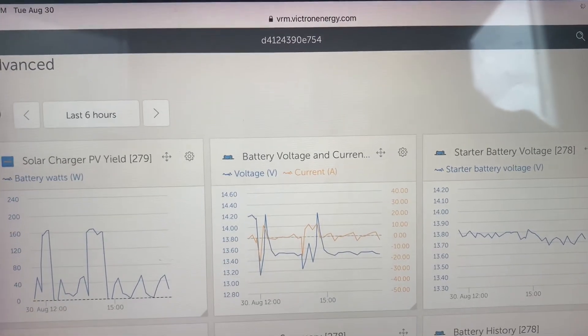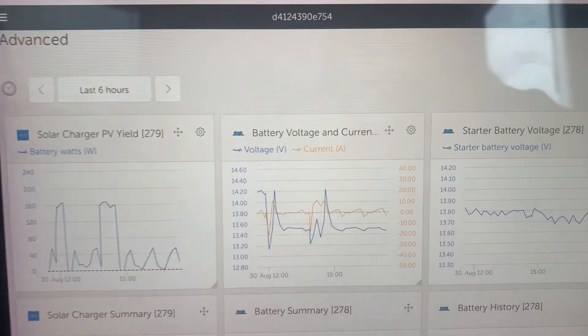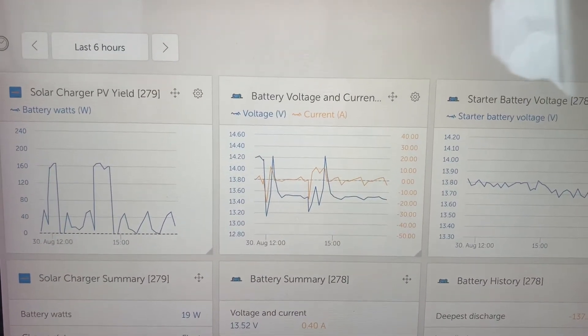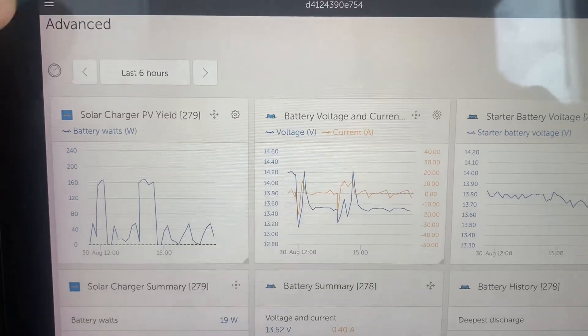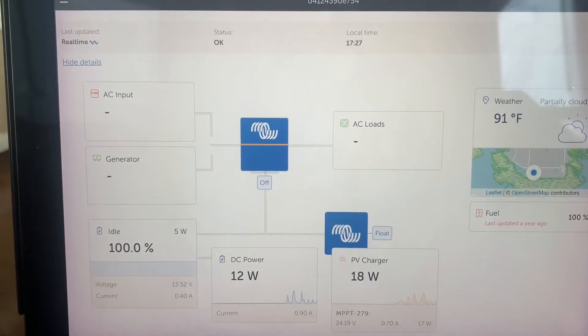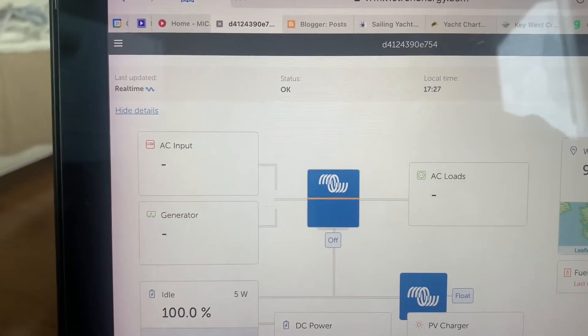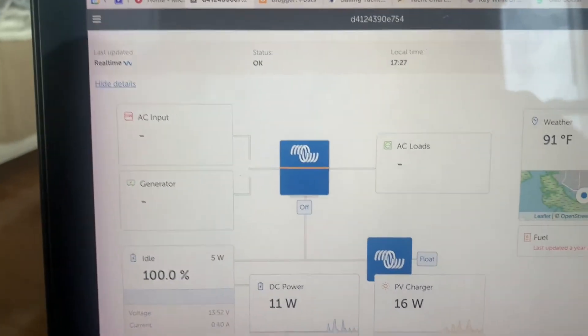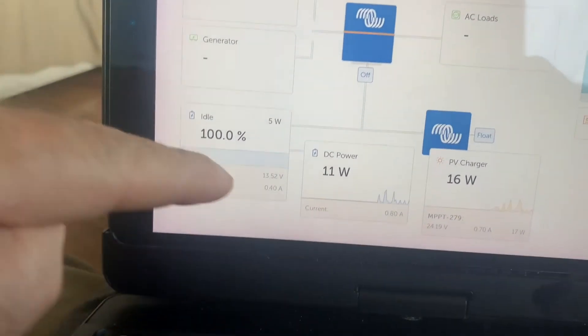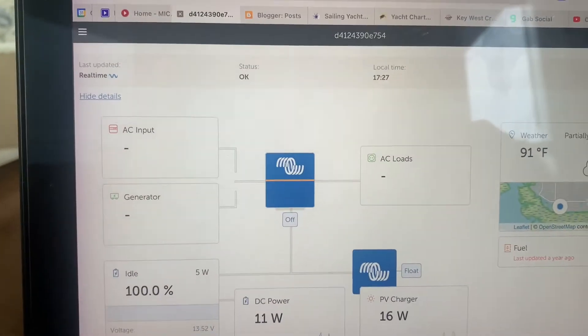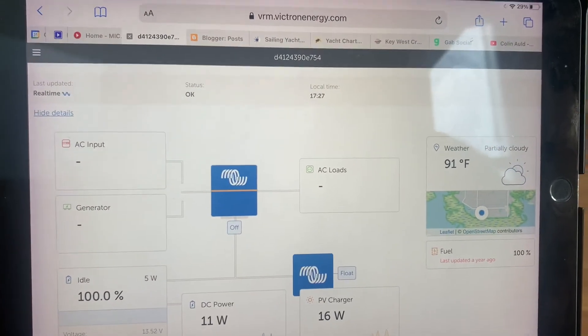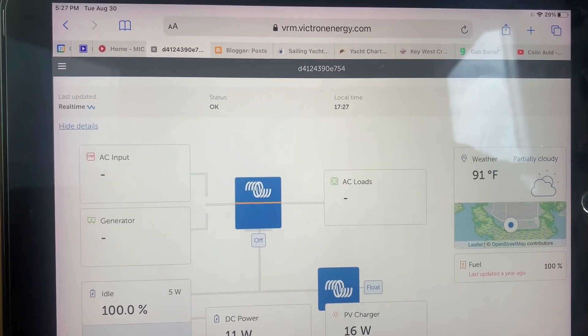I've set the rest of the house to 78. So it's not a full test like if it was the full 87 degrees like it is outside right now. Is it? Let's have a look. 91. Anyway, it's maintaining 76 degrees in there. And we are still at 100% on this battery. So I don't think we need too much more than a 200 amp hour battery to get us through the night as long as we get another day of sun tomorrow. We're going to see. I'm running this thing all night.